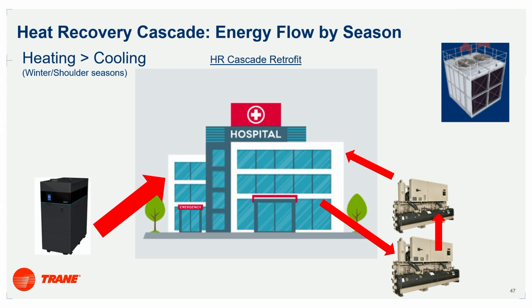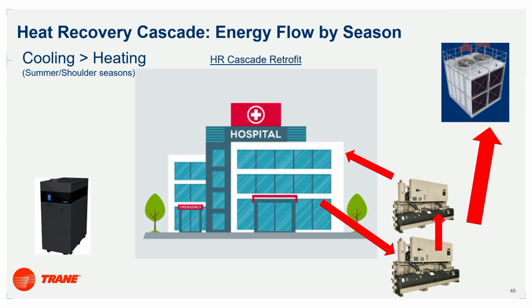So why not, instead of ripping this whole system out, add on to this system with a booster? When our heating is greater than our cooling load, rather than running our tower, we're going to keep those BTUs in the building. Extract that out of our building, put it through our standard chiller, put that into our booster to get 180-degree water. We're then going to handle the rest of the load with our hot water boiler. That's not going away. We need that natural gas infrastructure. Healthcare facilities have an 80% reduction goal by 2050. If we don't start taking measures now, we're not going to be able to get there in 2050 and just flip a switch. We've got to start taking the opportunities we have.